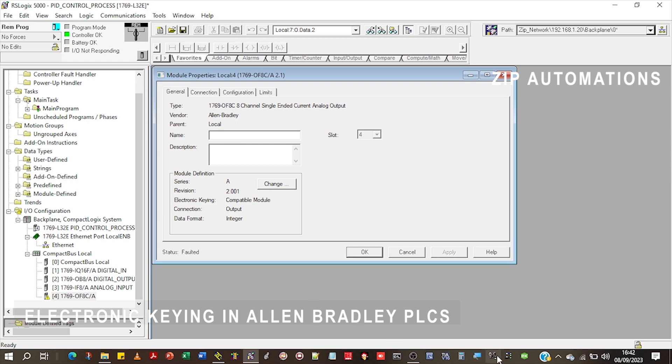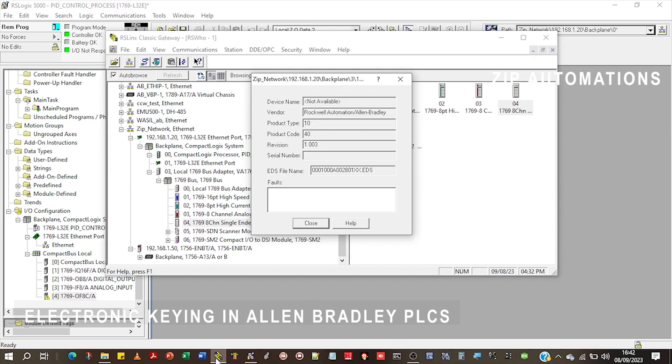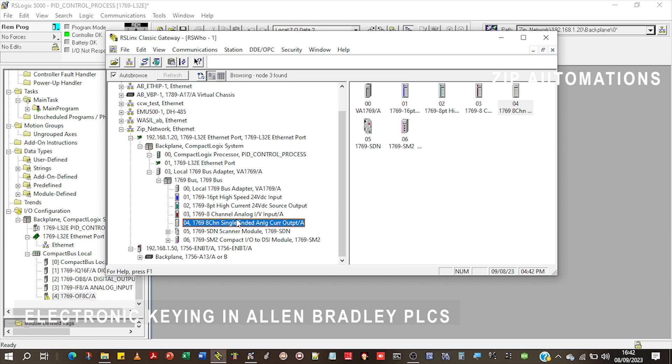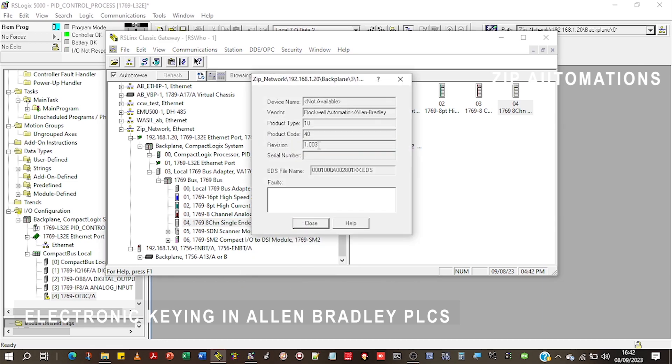If I go to my RSLinx, I can see the module here. It's an analog output on slot four. If I click on device properties, I can see that the revision is one and the major revision is one and the minor revision is three. The major revision is more important than the minor revision.